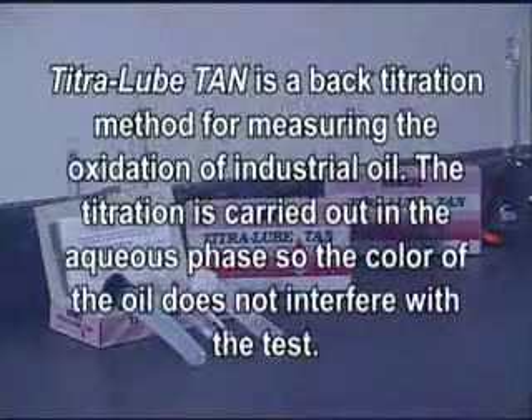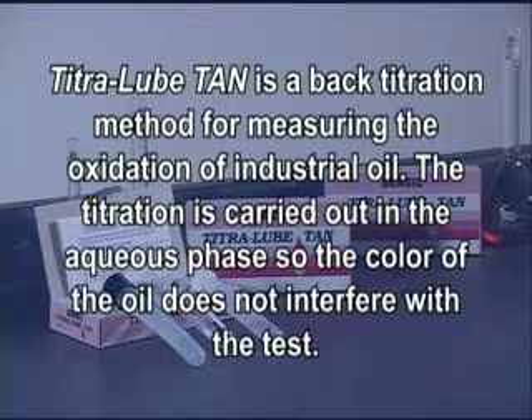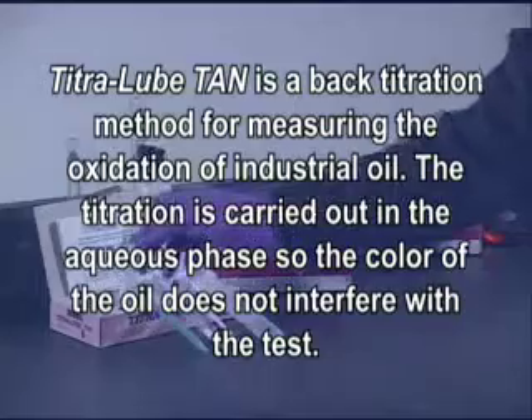Titra-Lube TAN is a back titration method for measuring the acid formation or oxidation of industrial oil. The titration is carried out in the aqueous phase, so the color of the oil does not interfere with the test.